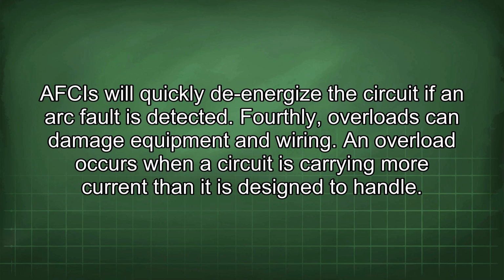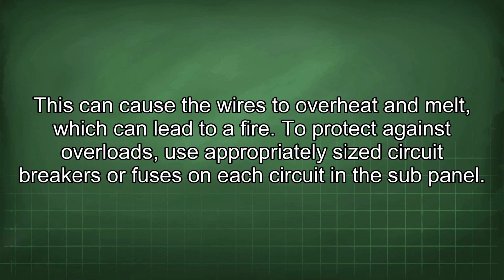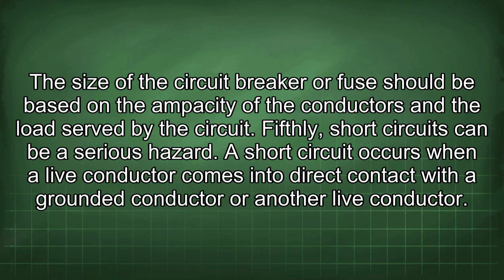Fourthly, overloads can damage equipment and wiring. An overload occurs when a circuit is carrying more current than it is designed to handle. This can cause the wires to overheat and melt, which can lead to a fire. To protect against overloads, use appropriately sized circuit breakers or fuses on each circuit in the sub-panel. The size of the circuit breaker or fuse should be based on the ampacity of the conductors and the loads served by the circuit. Fifthly, short circuits can be a serious hazard.